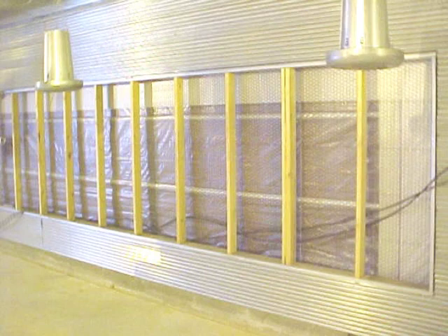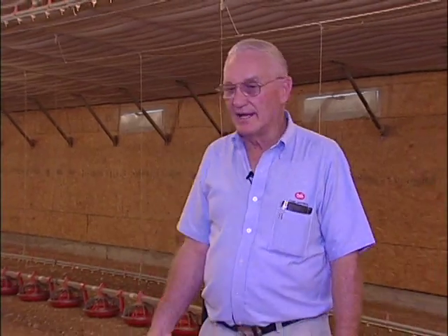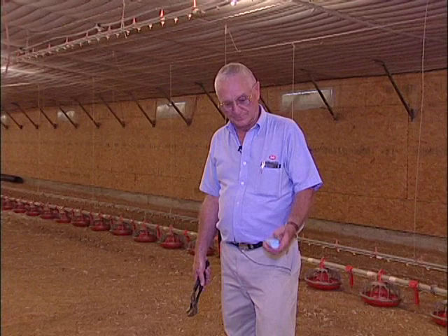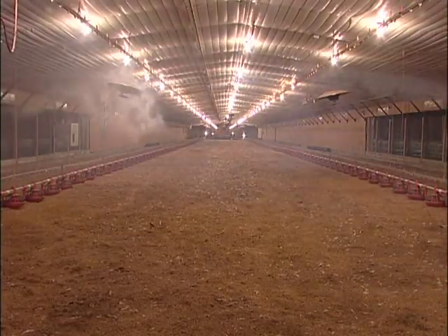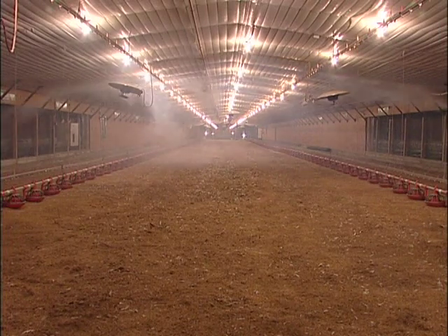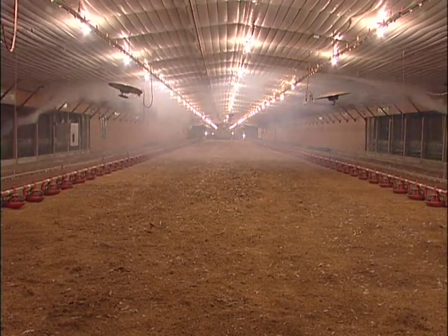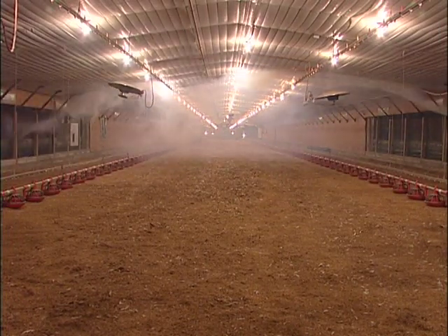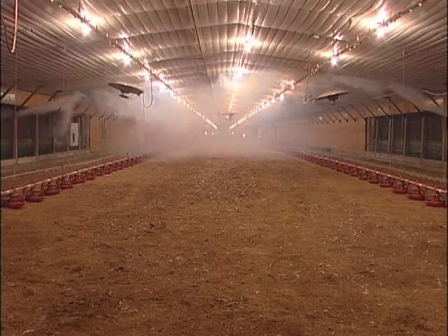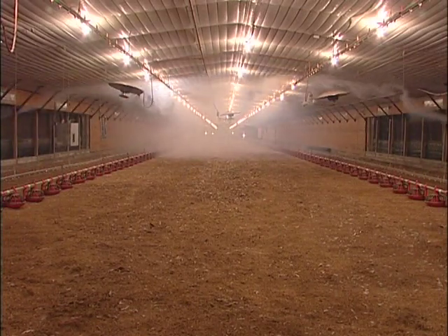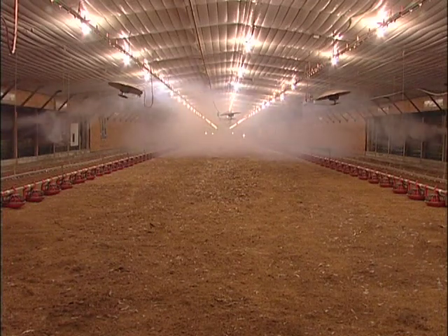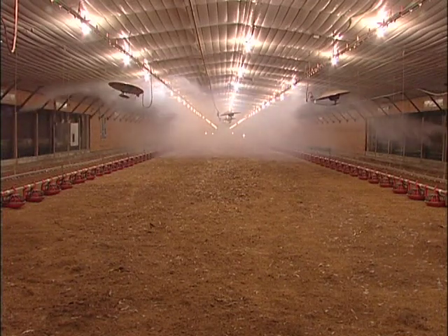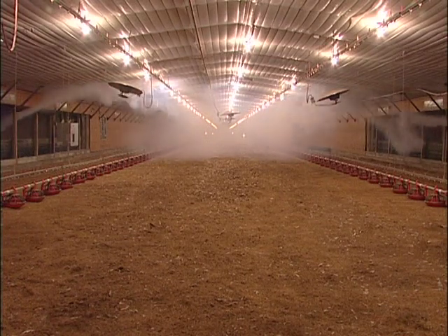All right, what we're going to do now is go down to the inlet area of the house, and we use smoke, as you've been seeing already, to allow you to see the air. We're going to let smoke come in both sides of the house down there, and you'll see the smoke come from one side to the center of the house, from the other side to the center of the house, and then it'll leave that end of the house and come through the house evenly all the way.